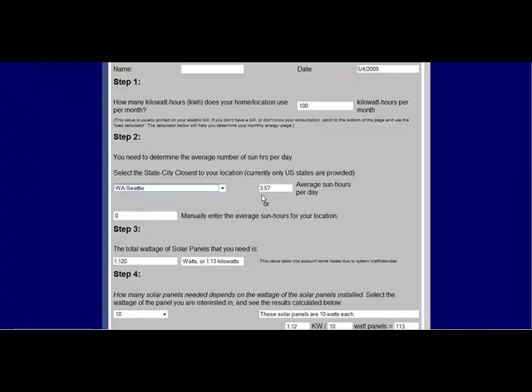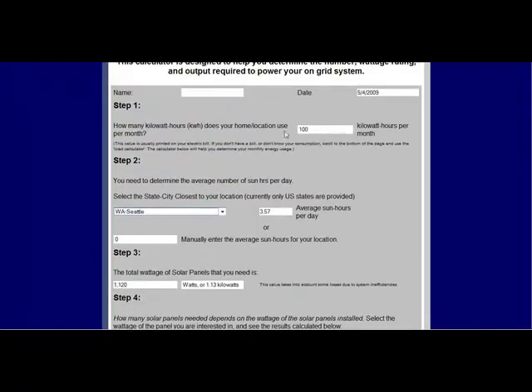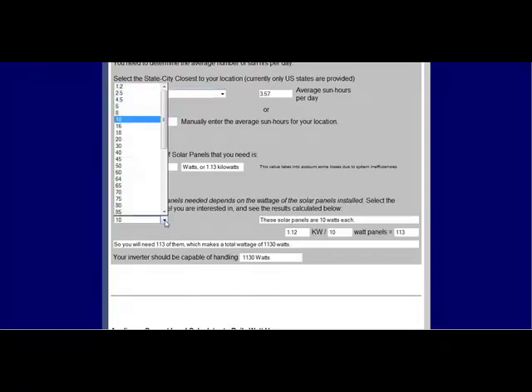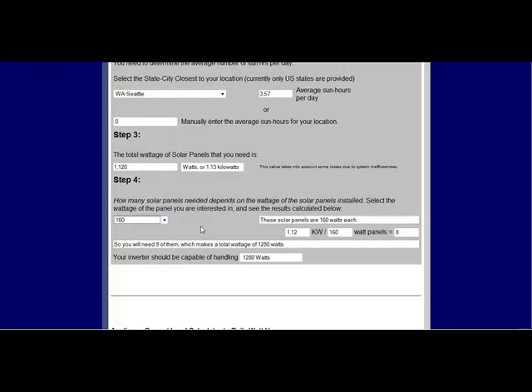If I go down here, then it's already calculated the total wattage of solar panels that I would need based on what we entered for our usage and where we live. The number of solar panels is going to depend on the wattage that those solar panels are putting out. If I buy solar panels that produce 160 watts, then I would need eight solar panels to give me the wattage I would need to power my home.